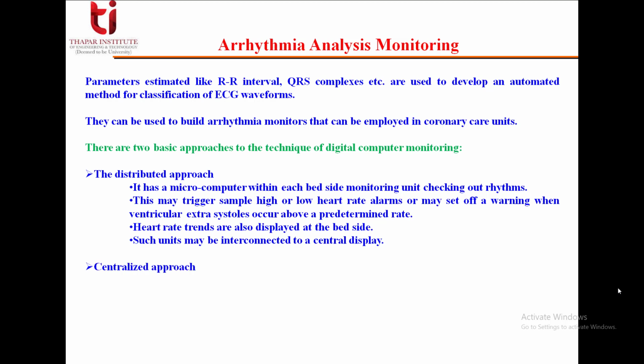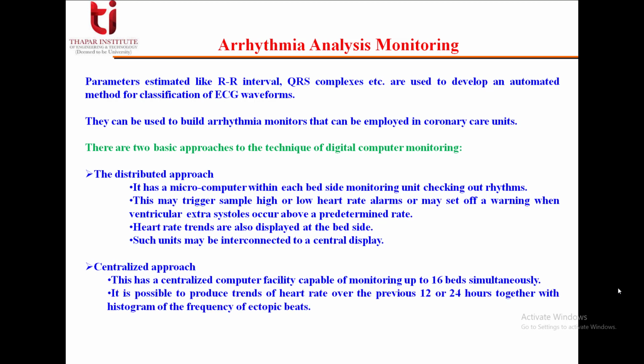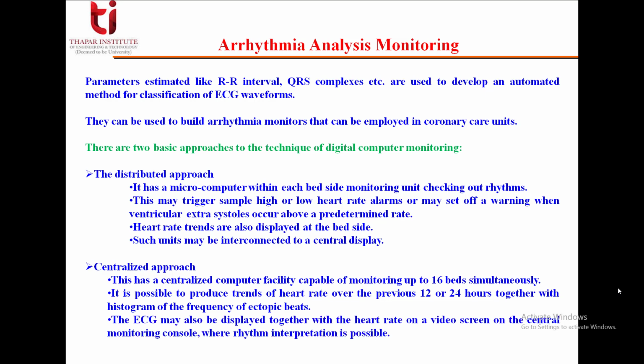Now we have another approach, that is the centralized approach. This has a centralized computer facility capable of monitoring up to 16 beds simultaneously. It is possible to produce trends of heart rate over the previous 12 or 24 hours, together with a histogram of the frequency of ectopic beats. The ECG may also be displayed together with the heart rate on a video screen on the central monitoring console, where rhythm interpretation is possible.